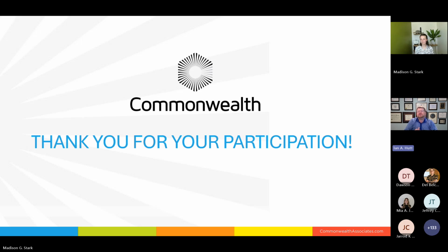Moving on to questions. This was from early in the presentation. How do you address when the utility X/R is higher than the UL489 molded case breakers X/R ratio? Now, I don't know if we can answer specifically the UL rating, but if the X/R from the utility is higher than the X/R ratio of the breaker spec, what do we do? Madison, any thoughts on that?